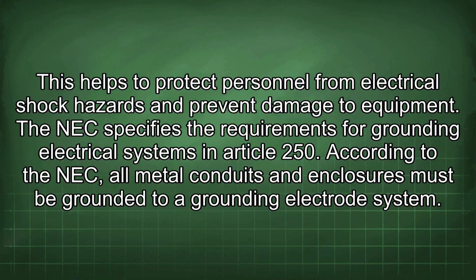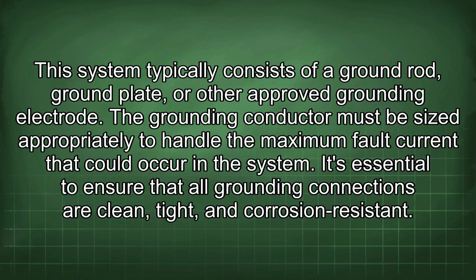The NEC specifies the requirements for grounding electrical systems in Article 250. According to the NEC, all metal conduits and enclosures must be grounded to a grounding electrode system. This system typically consists of a ground rod, ground plate, or other approved grounding electrode. The grounding conductor must be sized appropriately to handle the maximum fault current that could occur in the system.